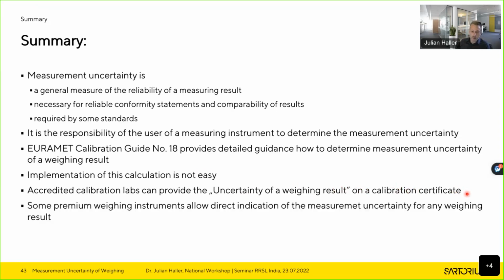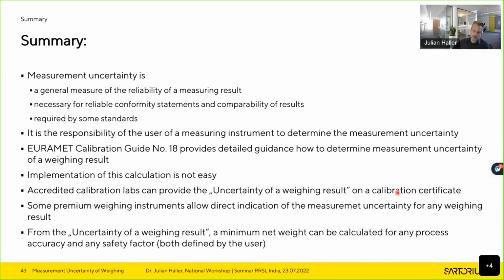As mentioned, some weighing instruments allow the direct indication of the measurement uncertainty for any weighing result if the respective straight line equation has been determined before. And just to finish that, from the uncertainty of a weighing result, a minimum net weight can be calculated for any process accuracy and any safety factor. Both have to be defined by the user. And let me mention that additionally, because there is a minimum net weight also according, for example, to the United States Pharmacopoeia. Do not mix that up.